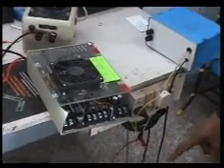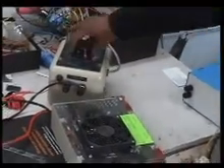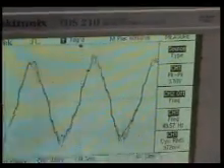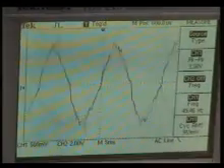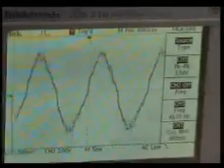Here I connected the load also. Now I am going to apply the voltage — see the waveform. Now see the current waveform — I will expand the current waveform. So now the power factor is 0.99. This is the conventional algorithm; up to this only we can achieve. But okay, that is also a better power factor.